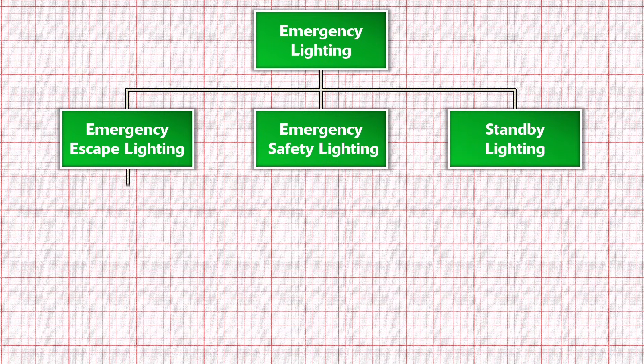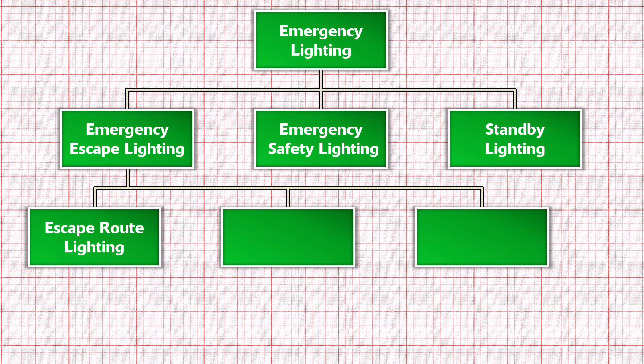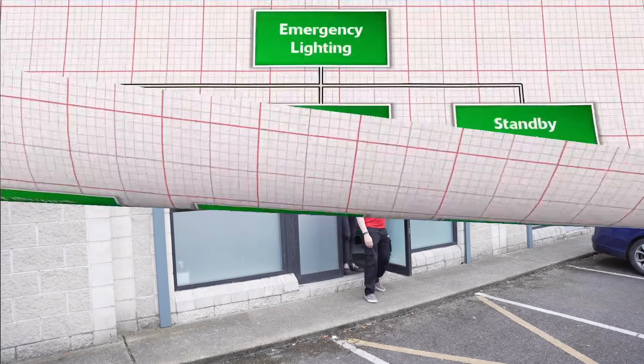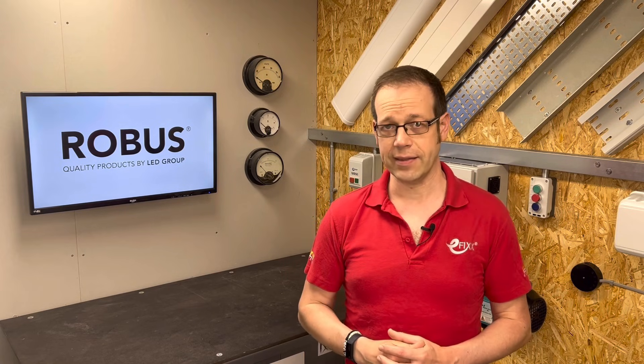First up is emergency escape lighting, which is broken down into three further categories. The first is escape route lighting. In a large building, there are designated routes to get out in an emergency, and one requirement is to have emergency lighting that illuminates the route sufficiently to allow people to see their way to a place of safety — usually the outside. This category also includes a sub-category covering safety signs, illuminating firefighting and safety equipment that may be needed in an emergency. This sub-category is so important that a whole video is devoted to it later in the series.